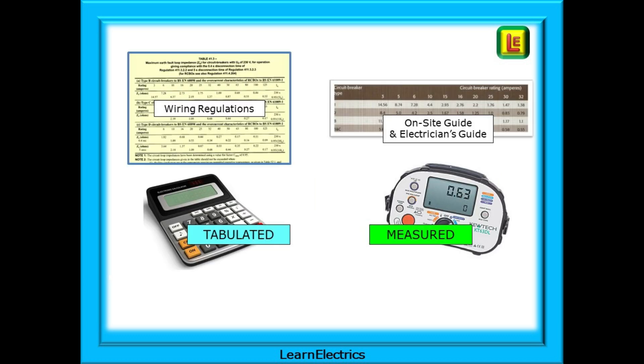Do try and remember this. They will try and catch you out with it in exams. The wiring regulations, the big brown book, gives us tabulated values of ZS. The on-site guide gives us measured values, those that we measure with our test meters. And get them the wrong way around and your schedule of test results will not look right either.